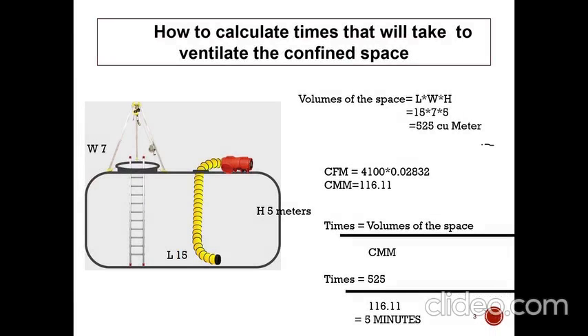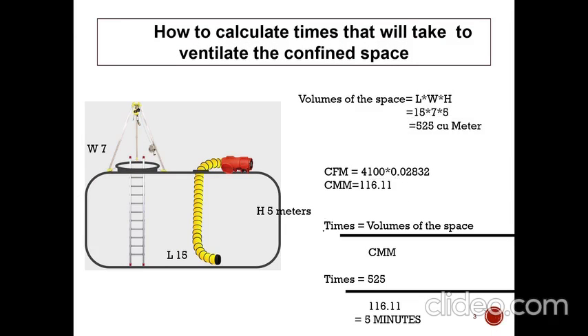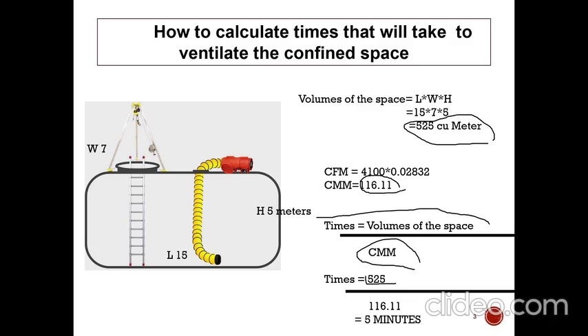We have already found the volume of the space, which is 525 cubic meters, and the CMM of the ventilation blower, which is 116.11. Using the formula: time equals volume of the space divided by CMM, time equals 525 divided by 116.11, and the answer is approximately 5 minutes.